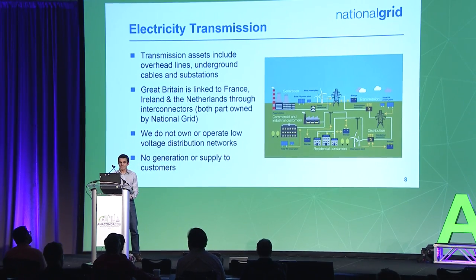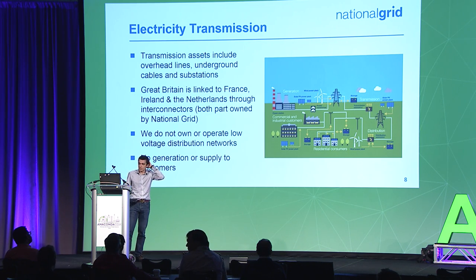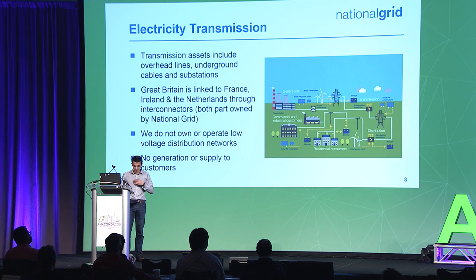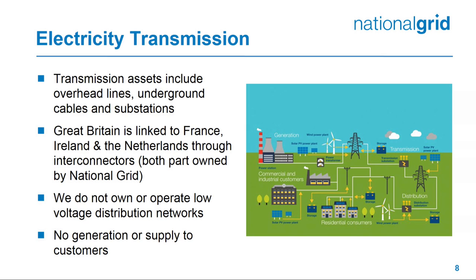Electricity transmission typical assets include overhead lines, underground cables, and substations. Our high-voltage networks run at 400,000 volts and 275,000 volts. Great Britain is linked to France, Ireland, and the Netherlands through interconnectors, with two more planned to Belgium and Norway, each about a gigawatt. We don't operate low-voltage distribution networks and we don't have any generation, nor do we supply directly to customers — though the US business does.